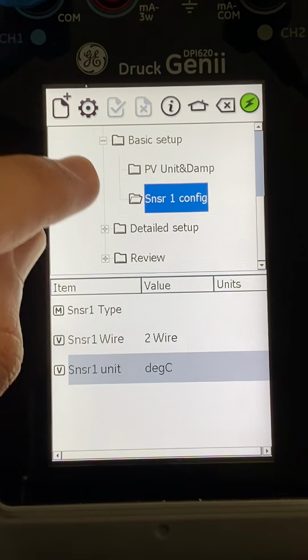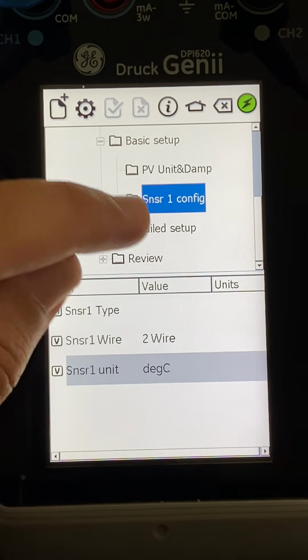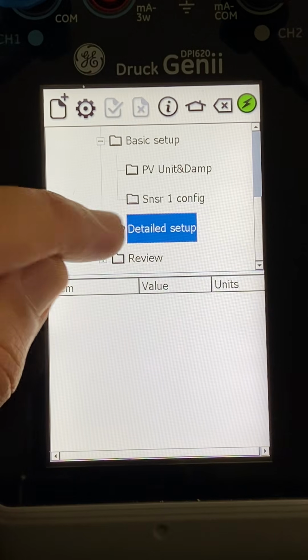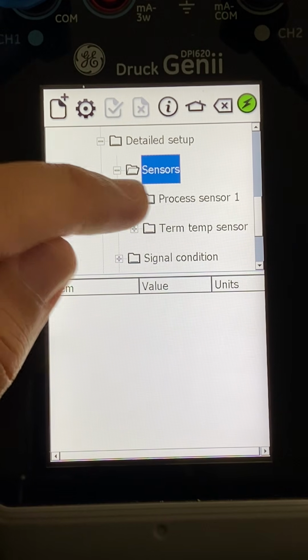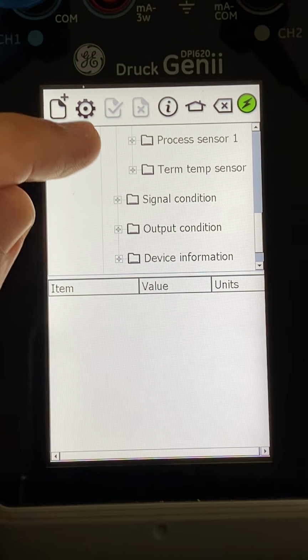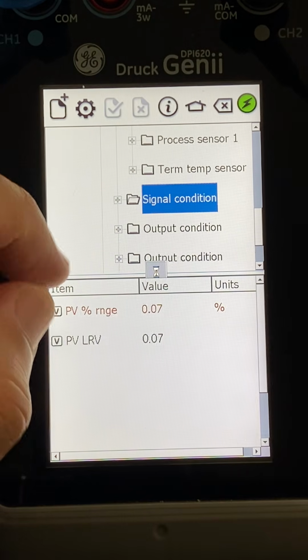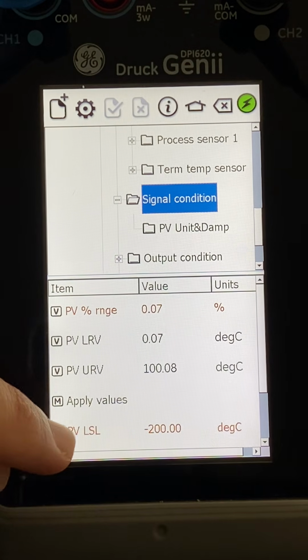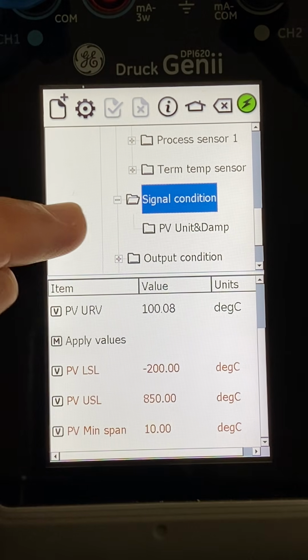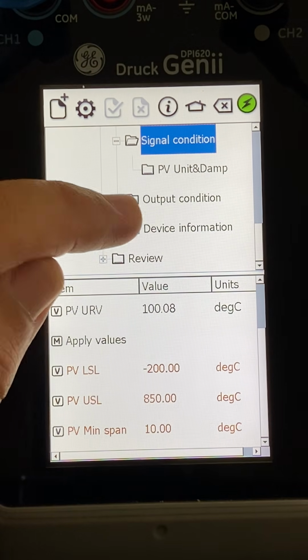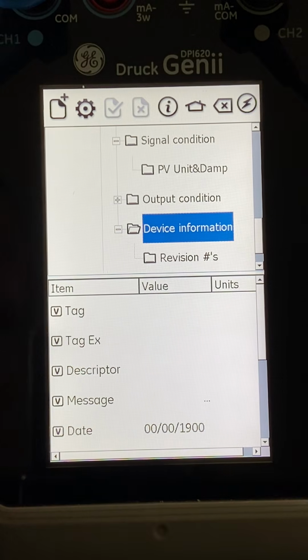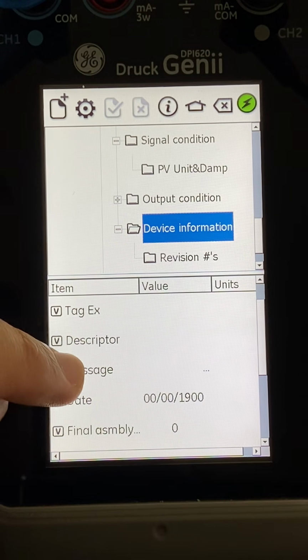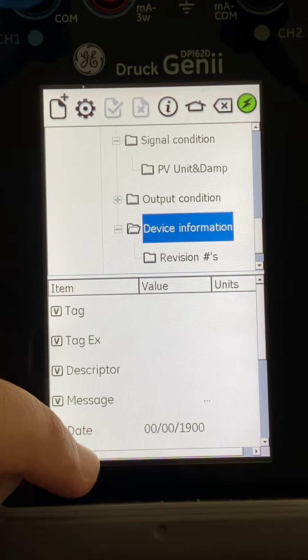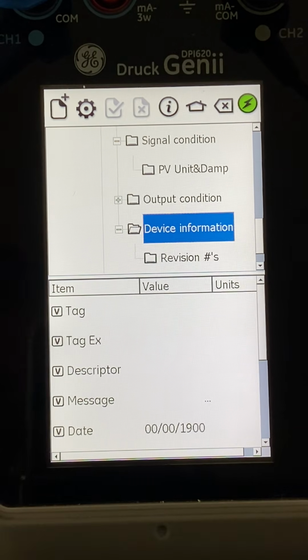So these are the basic HART functions. Let's browse and see more about setup. So in detailed setup, we have the temperature sensor, trim, signal conditioning, output conditioning, all of the HART functions. So it's a fully functional HART communicator. These are the diagnostics: the tag number, serial number, date, manufacturing date, manufacturer. So these are all set by the manufacturer.